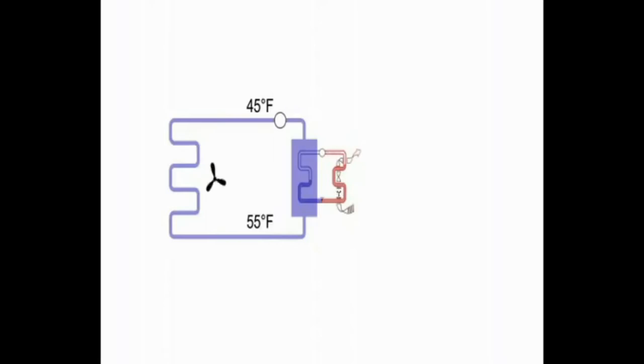The air handling unit then blows air across coils of chilled water rather than coils of chilled coolant as we saw in previous examples, thereby cooling 70 degree return air to 50 degrees for distribution through ducts.